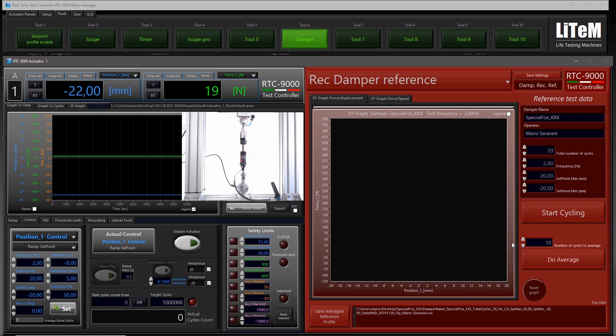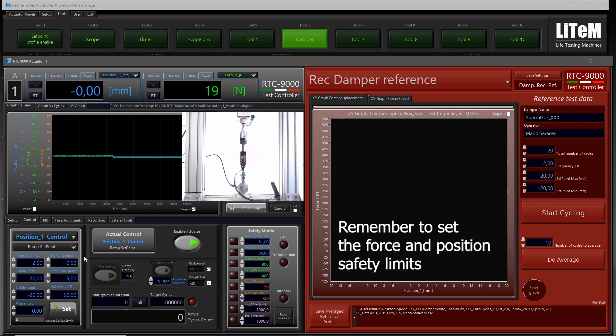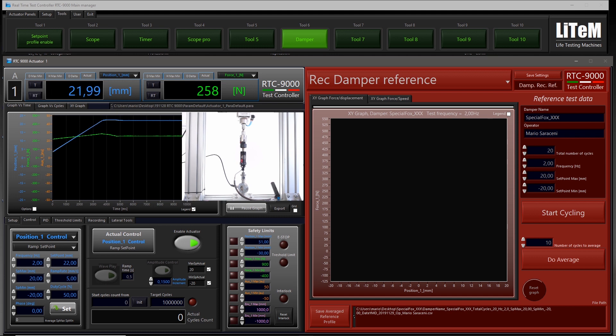This is the panel for recording the reference. I know that this actuator has about 44 millimeters for the full stroke. The damper is fully extended, so I will reset the displacement here. Now I enable the actuator and go to the middle stroke — 22 millimeters. Once the position is stable, I reset the displacement again with this button.